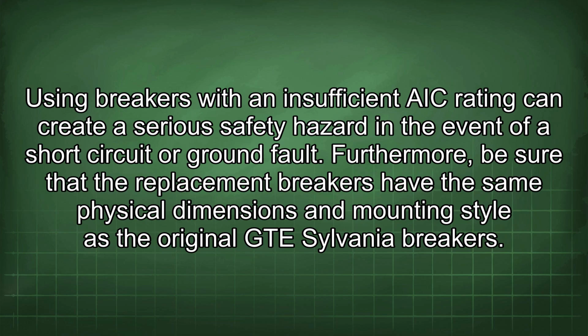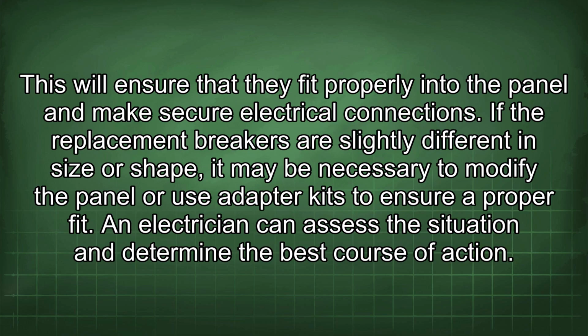Furthermore, be sure that the replacement breakers have the same physical dimensions and mounting style as the original GTE Sylvania breakers. This will ensure that they fit properly into the panel and make secure electrical connections. If the replacement breakers are slightly different in size or shape, it may be necessary to modify the panel or use adapter kits to ensure a proper fit. An electrician can assess the situation and determine the best course of action.